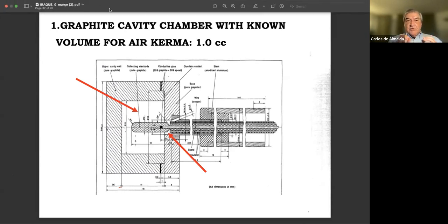Now you remember that what we aim is to measure the dose in a particular point in air in the absence of the detector. But it's not possible to do that for cobalt. For instance, to use a free air chamber in cobalt, we would need a very big instrument, because we need a very large thickness of air to provide the electronic equilibrium. So we use a solid material like graphite, or we use PMMA also. As we do that, we're introducing some material that is different than air, or graphite or PMMA. So we have to make corrections for that, okay?